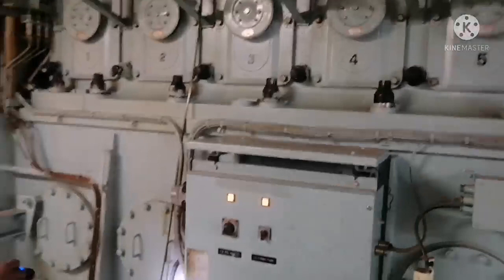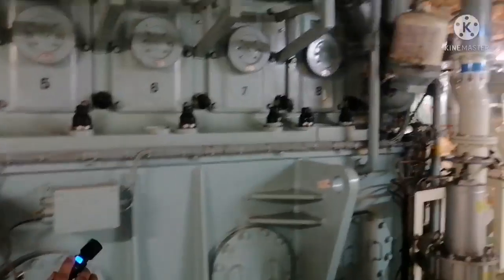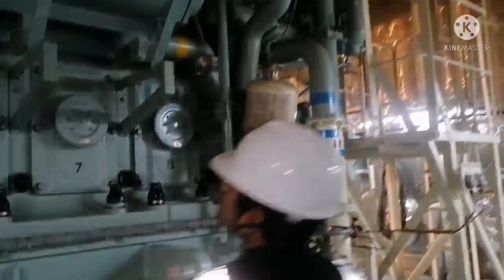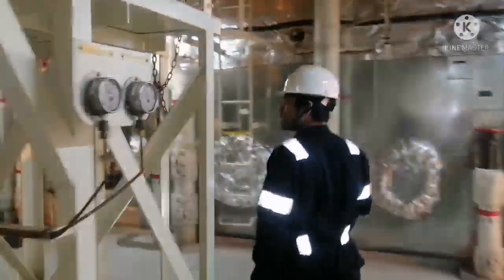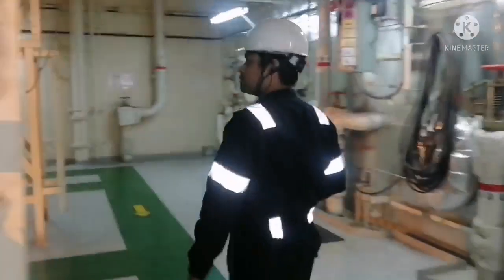And this is your main generator, diesel generator. And all you need to check is, if it is a running generator, you have to check for all the parameters, and you have to check for any leakages in the generator. Again, lube oil filter differential pressure should not be high, it should be normal, in the sense it should be within the green zone.